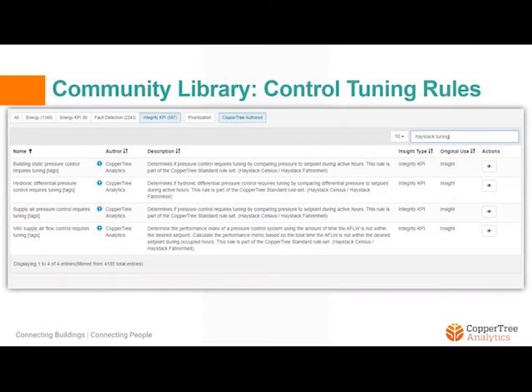Think about it this way. For your different equipment, air handling units, rooftop units, VAVs, fan coil units, unit ventilators, chilled water system, hot water system, name it, you are having multiple process variable control loops. For all of these control loops, you can use rules like this that will tell you how well the loops are tuned and if there is room for improvement.